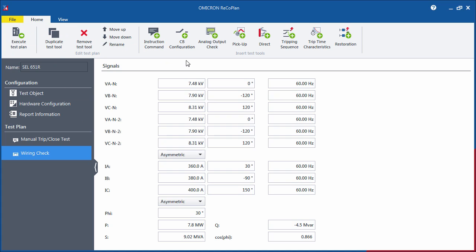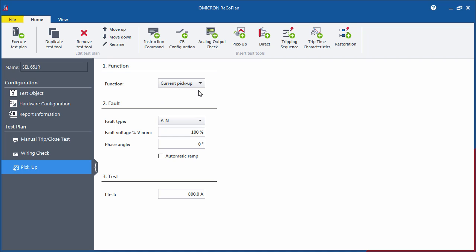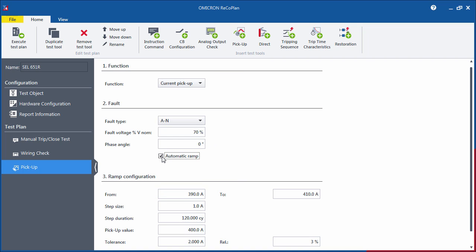The Pickup Test tool checks the thresholds of a specific protection function by ramping the current, voltage or frequency. Let's say that you want to test the current pickup function. Define the fault type and set the voltage to typical fault conditions, for example, 70% of the nominal value. The field for the test current specifies the starting value for the ramp.